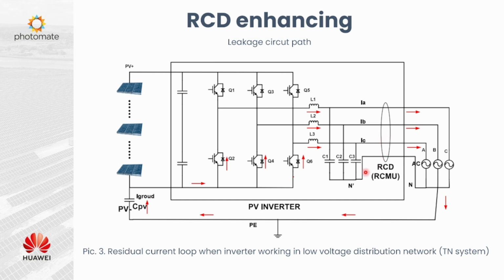There is also an RCMU, which is a residual current monitoring unit. But the threshold current for this is around 10 milliamps per 1 kilowatt of installed power.